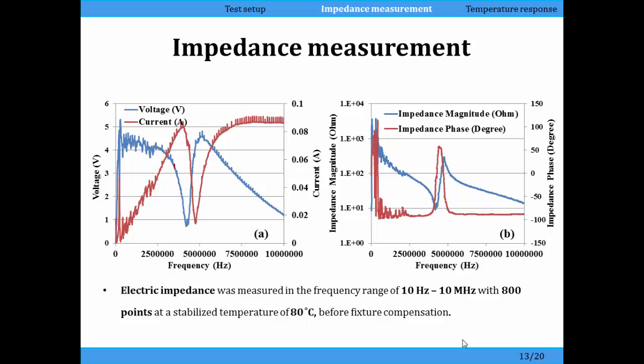These are the impedance measurements. On the left is the current and voltage — the direct output — there are lots of spiky bits, and my understanding is that those come from the beginning of each of the different frequency sets being measured, but that doesn't affect the output electrical impedance measurement on the right, which shows the magnitude and the phase.